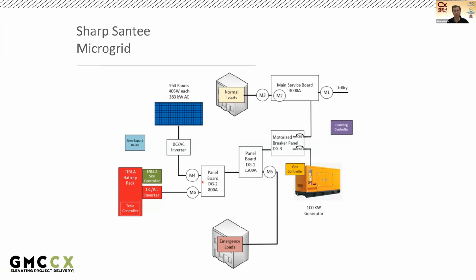This DG2 panel board is connected to a 1200 amp panel board DG1, which feeds emergency loads in the building. So here, diagrammatically, I'm showing 2 buildings. There's just one building, but that one building has emergency loads and normal loads. Here I'm showing 2, but in reality, it's just one building with the different types of loads.